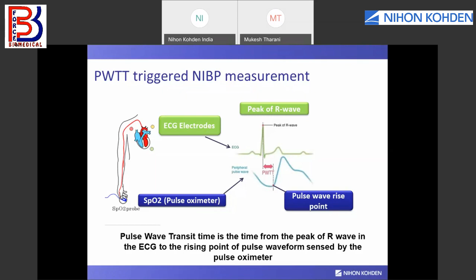Similarly, if the patient's blood pressure has gone down, the pulse will take more time to reach from the heart to the periphery, so the pulse transit time at that moment will increase. This is the principle we have applied in patient monitors. Whenever there is a sudden change in the patient's pulse transit time, which is calculated from the ECG and SpO2, the monitor triggers the NIBP measurement.